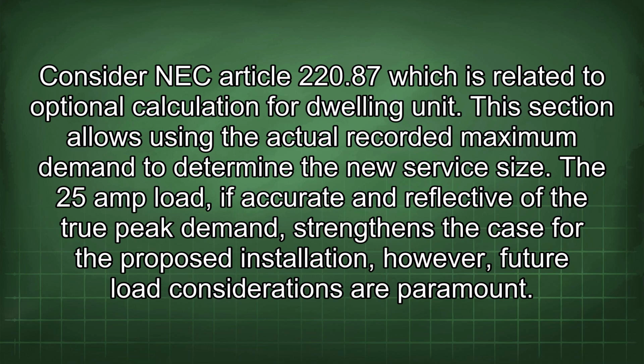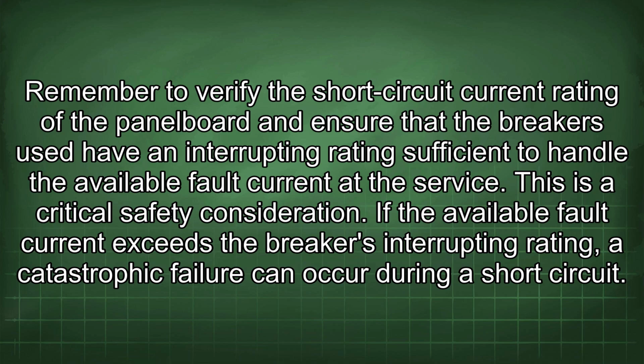Consider NEC Article 220.87, which is related to optional calculation for dwelling unit. This section allows using the actual recorded maximum demand to determine the new service size. The 25 amp load, if accurate and reflective of the true peak demand, strengthens the case for the proposed installation. However, future load considerations are paramount. Remember to verify the short circuit current rating of the panel board and ensure that the breakers used have an interrupting rating sufficient to handle the available fault current at the service.